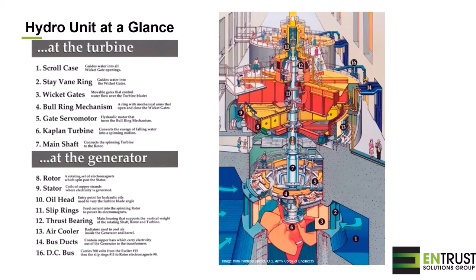The water will pass through the runner here, number 6. In this case, it's a Kaplan because we see that it has a variable pitch for the blade. The pitch for the blade is controlled completely at the top, number 10, what we call the oil head. So we have a set of shaft that will drive with a piston acting here, a set of mechanism to operate the blade opening. So the energy that is being converted from the kinetic energy will go through the main shaft, number 7, and drive the rotor of the generator, number 8.